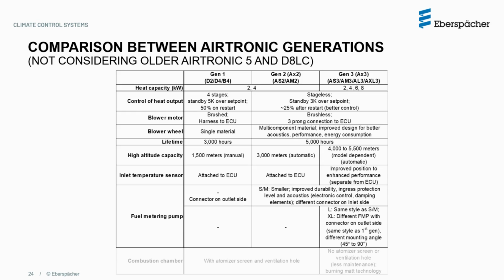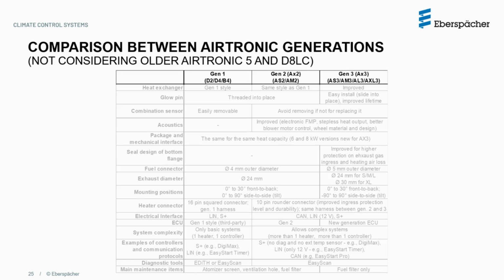The big difference is in the extra large size pump, as I mentioned before. One of the big differences in third generation is the combustion chamber, with no more atomizer screen and ventilation hole, since it uses a burning mat technology, reducing the amount of maintenance required. A few more. The heat exchanger has been improved in the third generation for an increased performance. The glow plug was previously threaded, and now it simply slides into place, having also an improved lifetime.